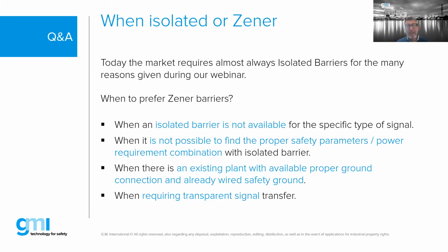For example, there's another type of barrier typically used for strain gauges, for weight scaling. Typically you have a barrier because you need millivolt to millivolt - you don't want to condition the signal, because the scale on the other end is designed to read the strain gauge directly. A few years back we developed an isolated barrier that transparently transfers the same strain gauge signal to the safe side through the isolation. It had to be specifically designed for that application, but it's a large application, so we did it. It's not that it can't be done, it just requires sufficient momentum to develop a barrier.